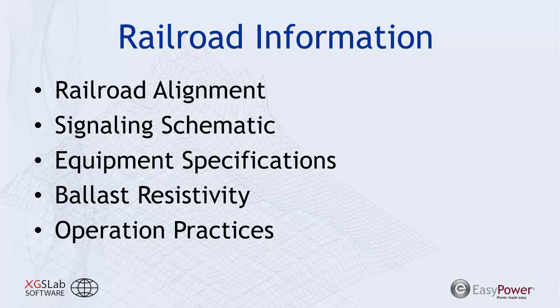For example, they may have the ability to operate with an insulated joint that is defective or is in need of repair, and that creates significant imbalance in the rail-to-rail voltage and can dramatically affect the downstream signaling when you incorporate AC interference into that. Or you could have train operators that will occasionally stop the train at different junctions, crossing over those insulated joints, elongating potentially the exposure length of that railroad to the transmission line.